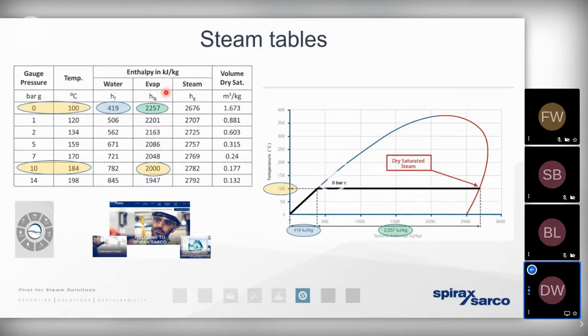So what we can see from the steam tables is by increasing the pressure, we've increased the boiling point of the water. We've therefore got to put more energy into that water to bring it up to boiling point. But we need to put less energy into the boiling water to make it evaporate to produce steam. The steam that is produced is going to have significantly more energy in it as we increase the working temperature. And of course, because we've increased the pressure, we've reduced the volume that mass of steam exists at. So what you can see is, as we manipulate the pressure, all of the values in this chart change.